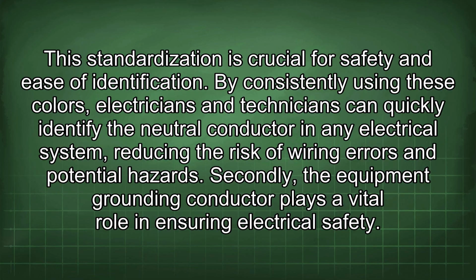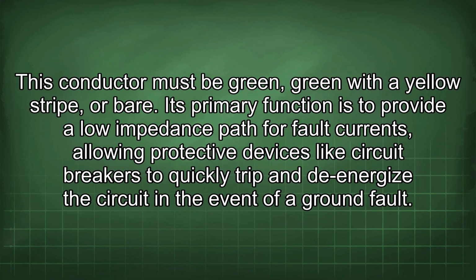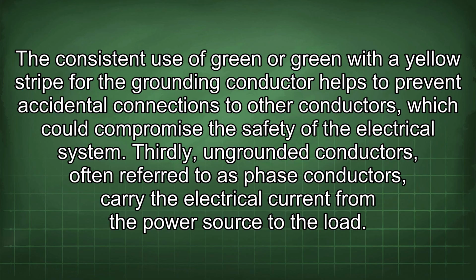Secondly, the equipment grounding conductor plays a vital role in ensuring electrical safety. This conductor must be green with a yellow stripe or bare. Its primary function is to provide a low impedance path for fault currents, allowing protective devices like circuit breakers to quickly trip and de-energize the circuit in the event of a ground fault. The consistent use of green with a yellow stripe for the grounding conductor helps to prevent accidental connections to other conductors, which could compromise the safety of the electrical system.